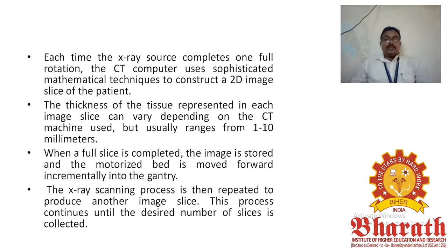When a full slice is completed, the image is stored and the motorized bed is moved forward incrementally into the gantry. The gantry is the outer structure where the patient moves inside. The X-ray scanning process is then repeated to produce another image slice. This process continues until the desired number of slices is collected.